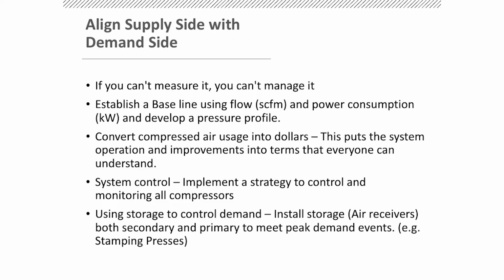So really it's about establishing a baseline, understanding what it is, putting it into dollars for improvements, looking at the system control and how we can control and monitor the compressors, and then using storage to help control, air receivers, secondary storage for some of the peak events that you have. In there is an important part, especially depending on the type of air compressors you have. Receivers are important, for example, in a load-unload control rotary screw.